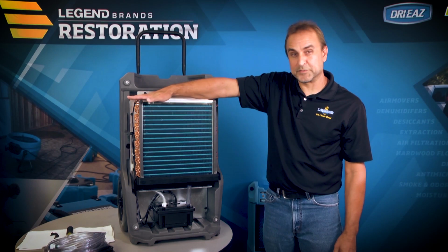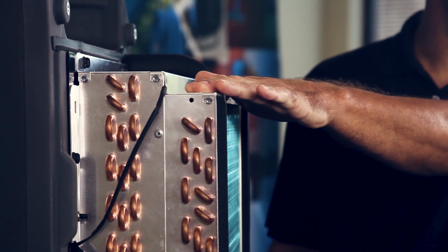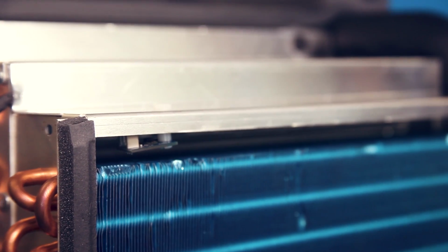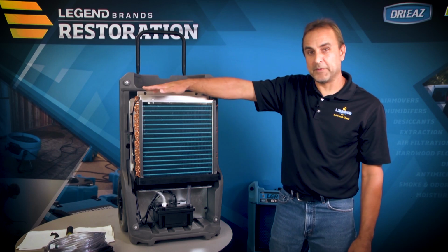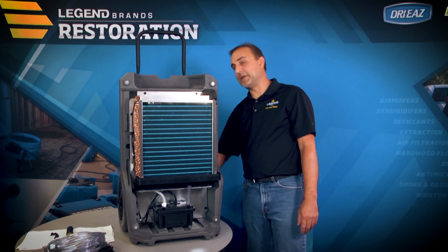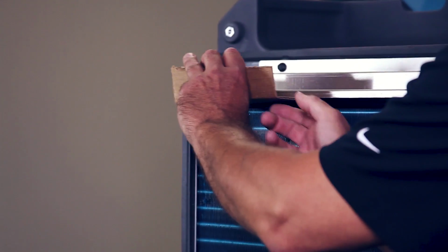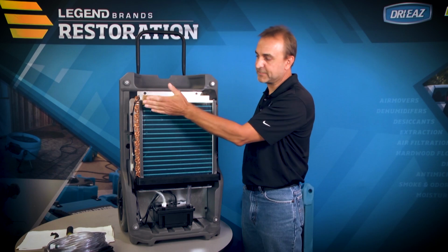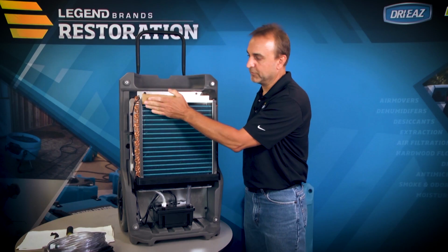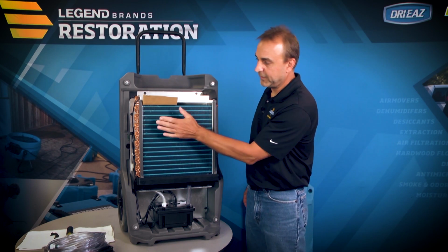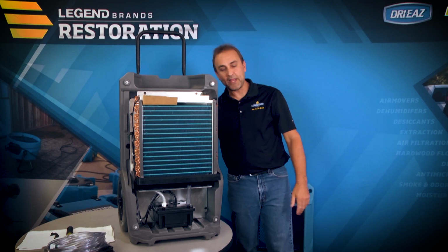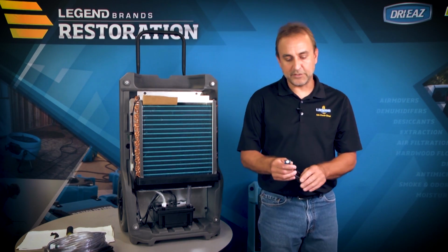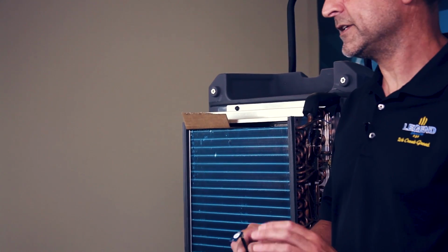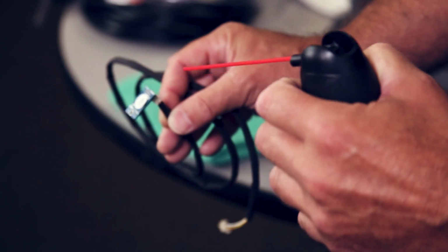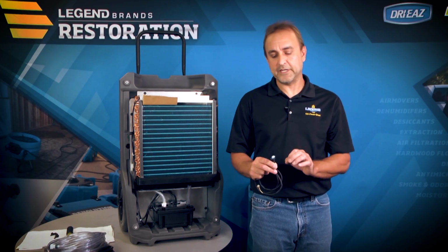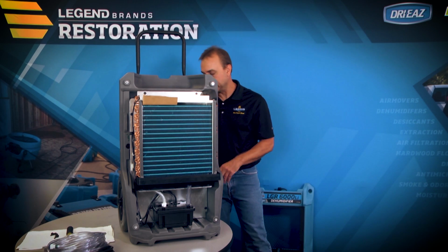Should you need to clean the inlet temperature and humidity sensor, you can access it at the top corner. The inlet temperature and humidity sensor will generate an ER5 error code if it needs attention. But when cleaning the coils, we'll want to make sure we protect that sensor from any cleaning solution or rinsing water. And the best way to do that is to put a piece of plastic or a piece of corrugated from a box top over that sensor, so when you're applying that coil cleaner, it doesn't splash up and damage the sensor. You may dry clean the inlet temperature and humidity sensor using a soft cloth or compressed air. If you're using compressed air in a can, make sure you do not invert the can and spray liquid on there. Again, liquid cleaning will damage that inlet temperature and humidity sensor.